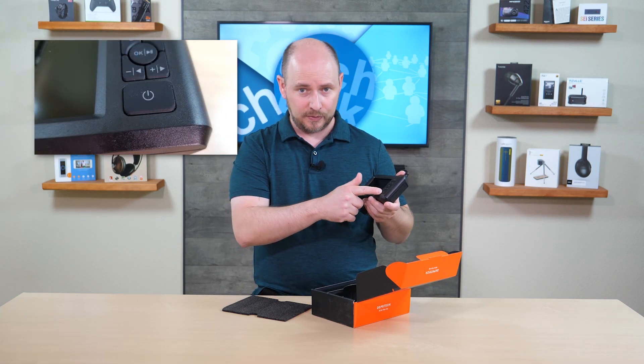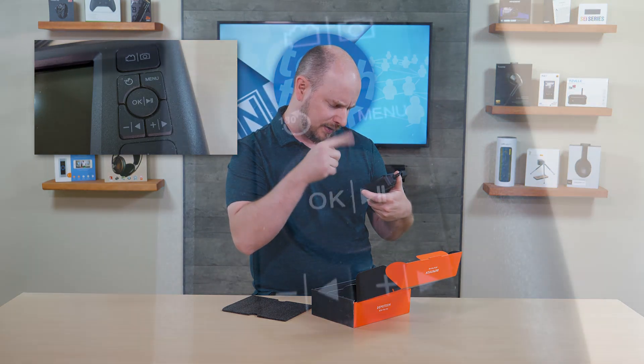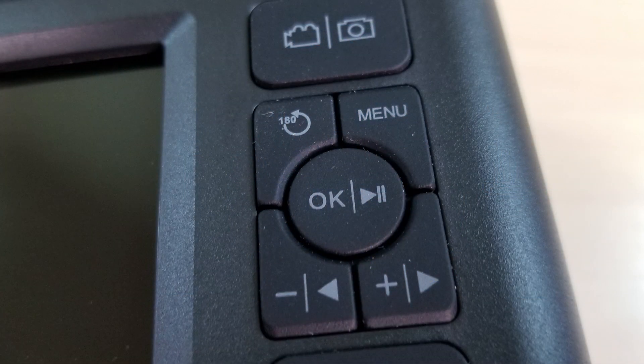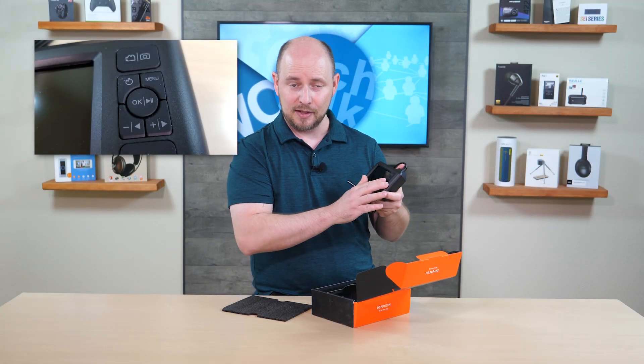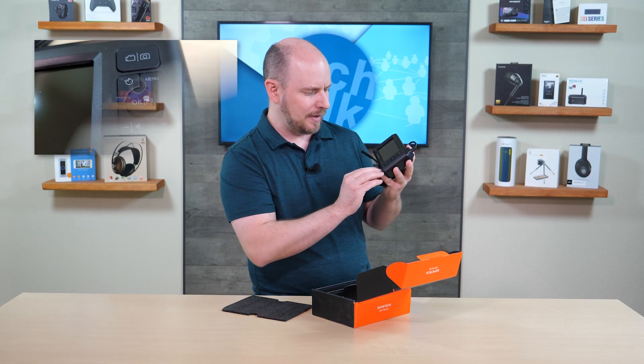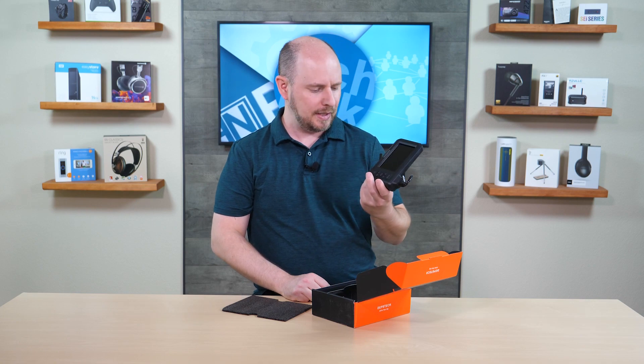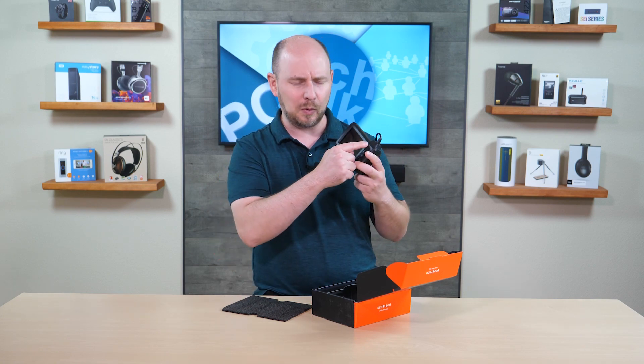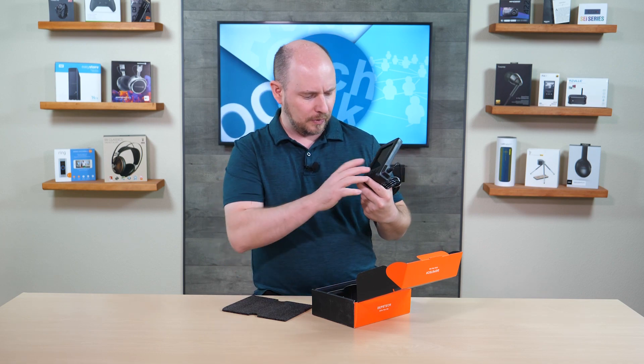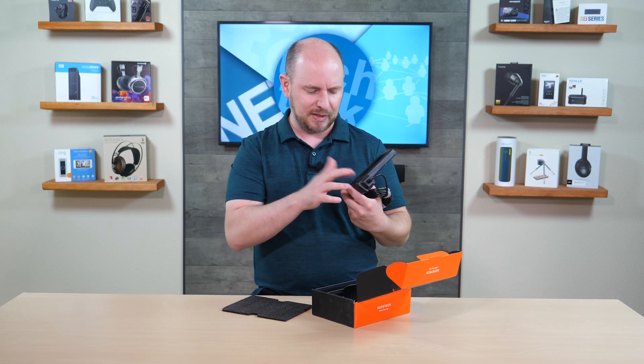The top button is for taking pictures and video — just point, click, and take a picture or start and stop a video recording. The bottom button is for turning the unit on and off. In the middle you have a 180-degree spin button, a menu button to access options, an OK/play/pause button for navigating the menu or playing back recorded videos, and next and previous buttons at the bottom. It's pretty simple — feed the snake into the area, hit record or take a picture, and you're done.